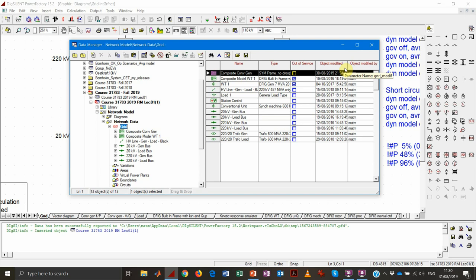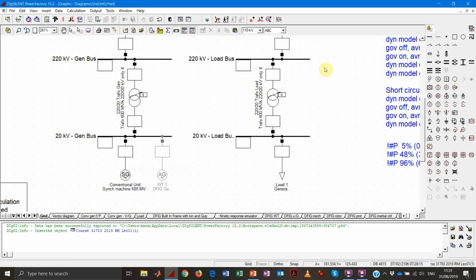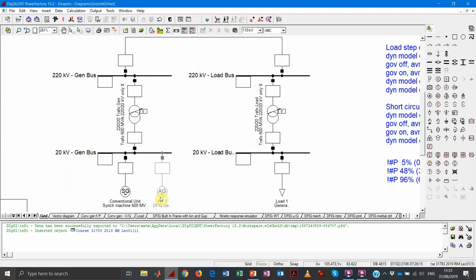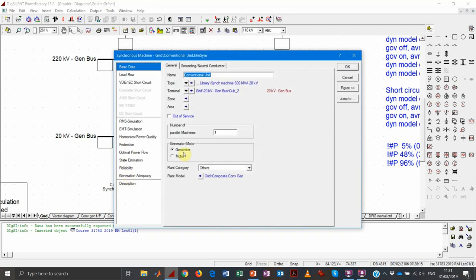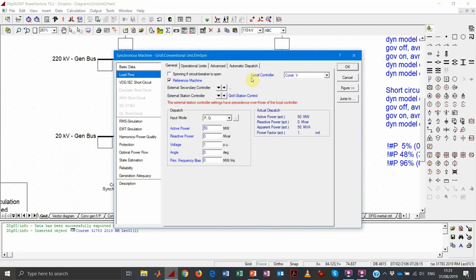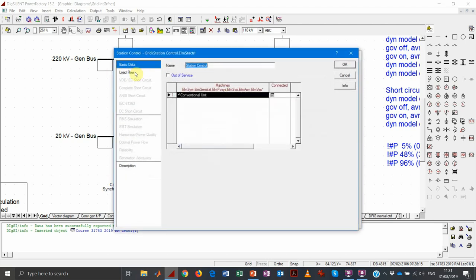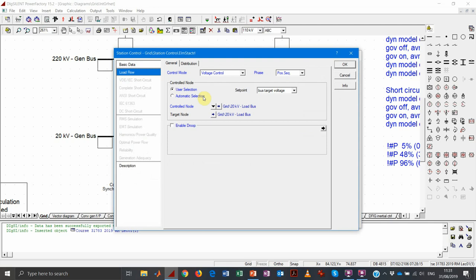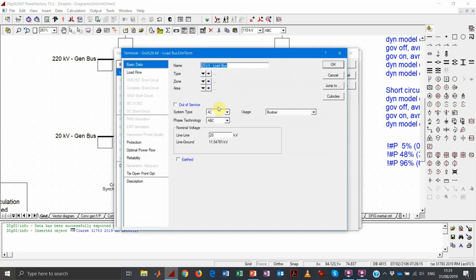Let's focus on this frequency event. We can see the various elements in the grid. We have the generator. Looking at the load flow page of the generator, we can see there is an element called station control, which replaces the local voltage controller. This element is the one that will make sure the generator controls the voltage at this bus according to a certain set point.